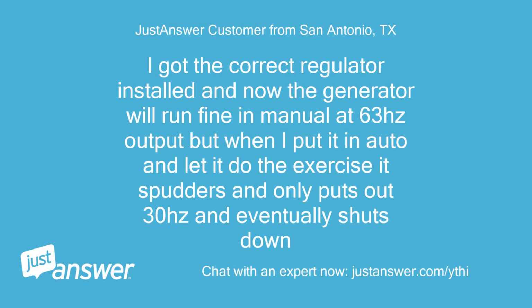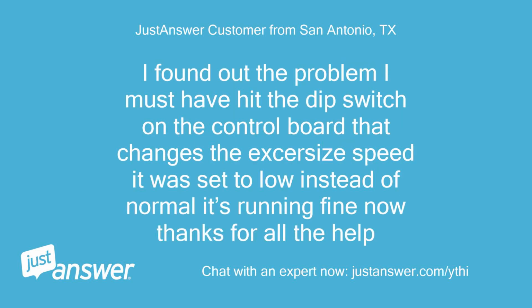I got the correct regulator installed and now the generator will run fine in manual at 63 Hz output, but when I put it in auto and let it do the exercise it sputters and only puts out 30 Hz and eventually shuts down. I found out the problem. I must have hit the dip switch on the control board that changes the exercise speed. It was set to low instead of normal. It's running fine now. Thanks for all the help.